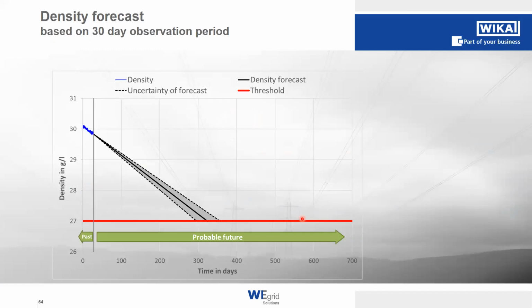So regarding the forecast, this is an algorithm that has been developed by WEGrid ourselves, and basically it is providing a time window that you can see here based on the data that it has collected in the past. And of course, the longer the observation period is, the more data it has collected, the more accurate the prediction will be. So you can see here, this is the uncertainty based on 30 days of observation of density, and based on 90 days, the uncertainty will of course be lower. So this algorithm is basically learning and improving over time the longer it has been installed to the GIS.